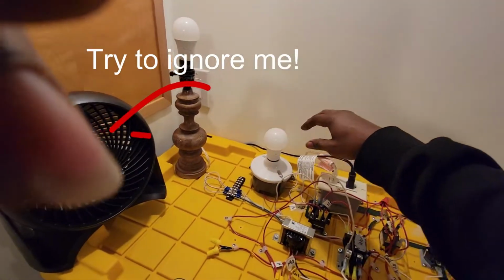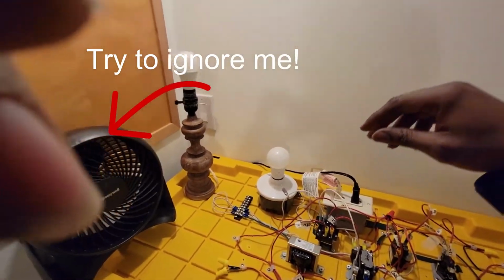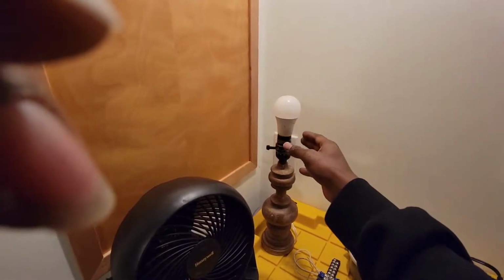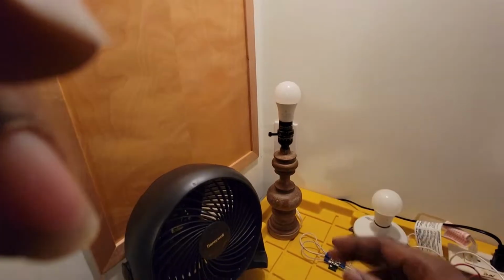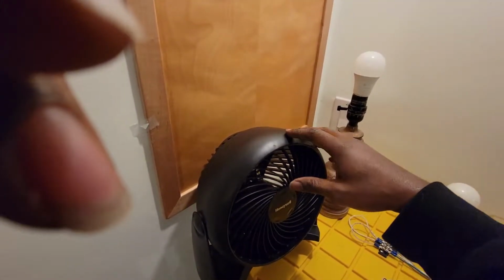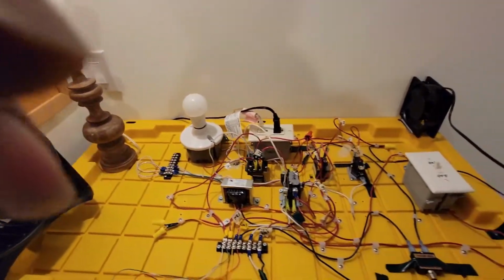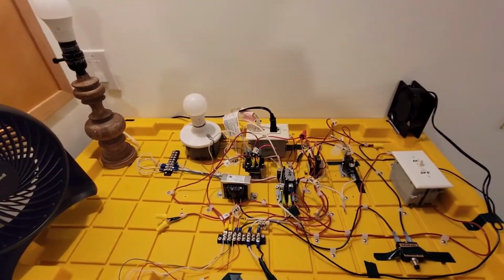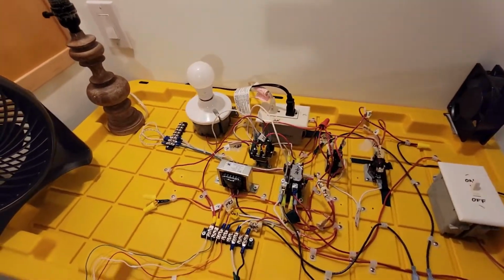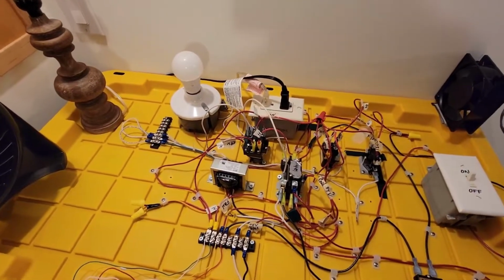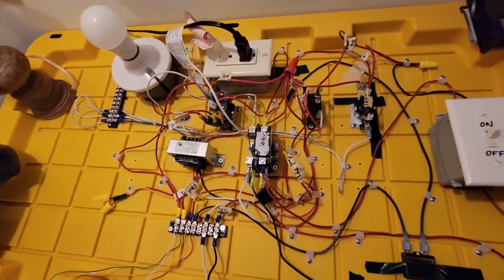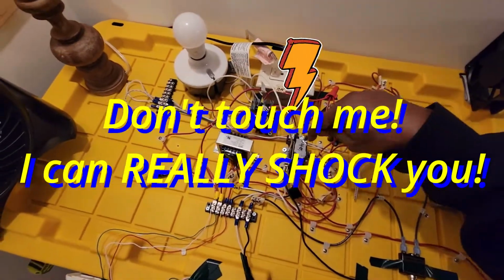Now I have my fan over here on the side, my 120 volt shaded pole fan. I have this lamp right here representing my heating system. I have this lamp right here representing my cooling system. This would actually be the compressor, and this would be the condenser fan. The condenser fan and the compressor are all wired into this receptacle over here, and that receptacle is controlled by the white wire, the Y wire, which is the cooling wire. That cooling wire is going through this contactor right here.